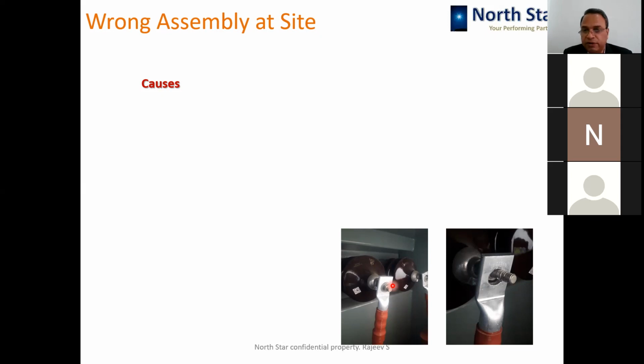Another problem that can arise later: look at the size of the hole in the lug and the stud metal part. This is a current-carrying portion, and significant heating can occur at this joint during service. It's no wonder that after a year or so, a complaint comes in about the metal part overheating, requiring replacement, or the transformer may even fail. Such small issues cause big pain for us.